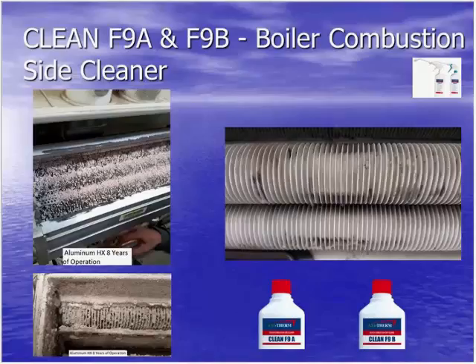But I had an aluminum block boiler like this that was on a horse barn. Mm-hmm. And the combustion air intake was 30 feet off the deck. But when the horses were running around outside, it would actually cause dust to go up, and we were inducing that into the combustion process. And that lower left-hand picture is what his burner assembly looked like after about 2 years. Oh, yeah. We ended up having to put an air filter on it in order to reduce the contaminants getting into the combustion process.